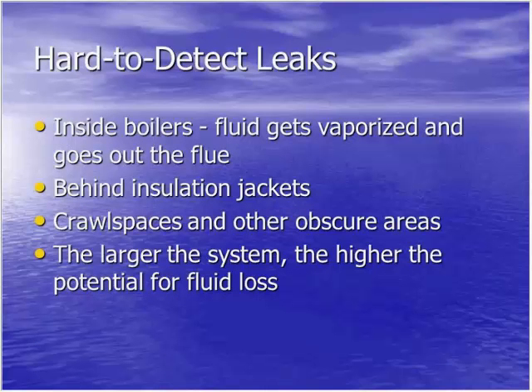Some leaks are hard to detect. They can happen inside boilers, on the heat exchanger. And in that case, the fluid would potentially get vaporized by the combustion and just go out the flue. Or I've seen leaky heat exchangers leak water through, and modern boilers have condensate traps or drains in the heat exchanger. So condensate or water can leak through the heat exchanger and down through the condensate drain. And no one would ever know. Some people see that the condensate line is draining condensate and are told that's a good thing because it's running efficiently.